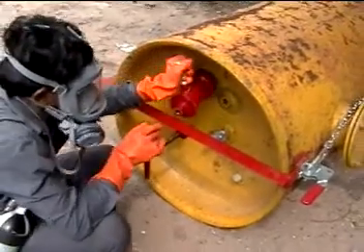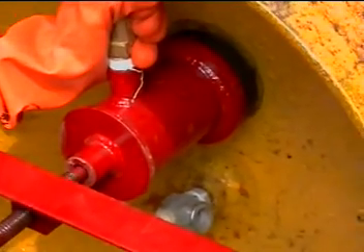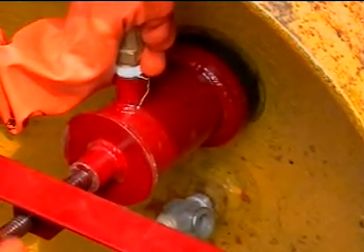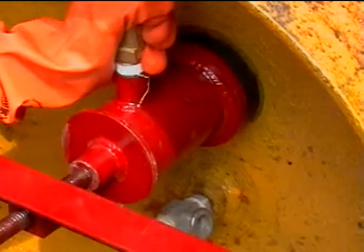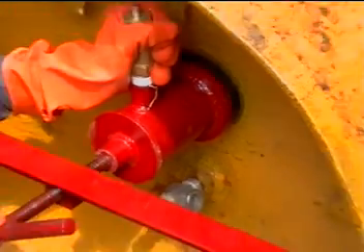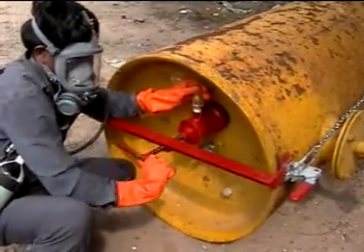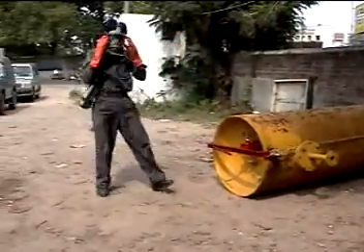After this, take the small hood on the left hand, keep the valve in the vertical position, and start fixing it on the leaking valve. Take the central key, adjust the position, and start tightening until you observe the chlorine flow completely stop from the valve.